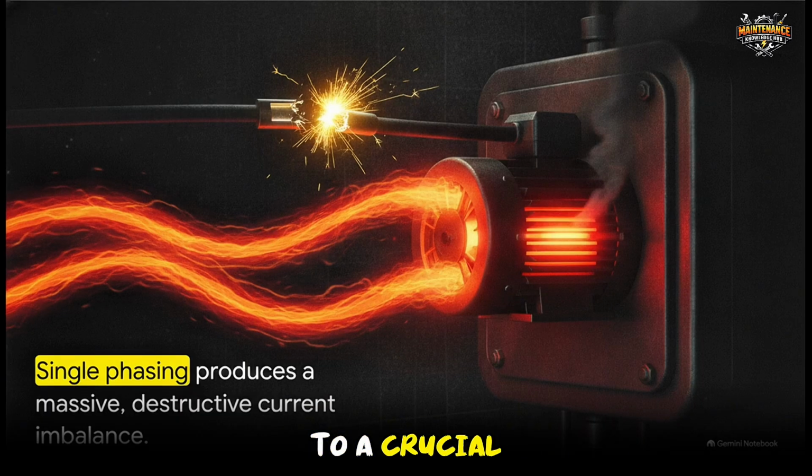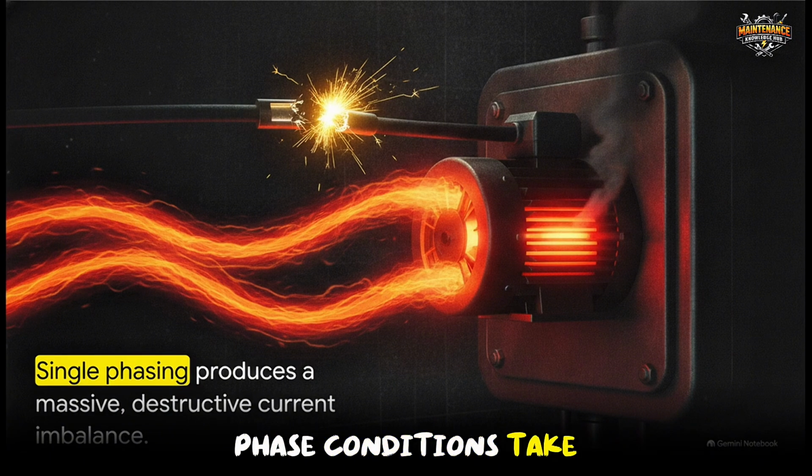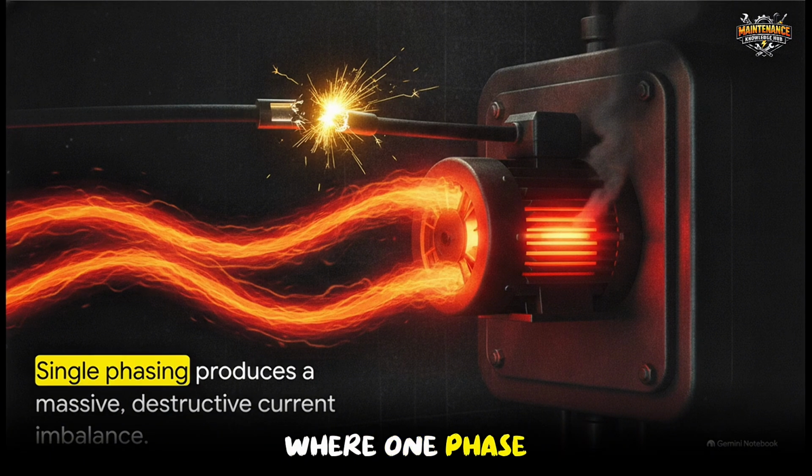This brings us to a crucial point. You must absolutely never allow a motor to operate under abnormal phase conditions. Take single phasing, for instance, where one phase of a 3-phase motor is totally lost because of, say, a blown fuse or a damaged cable. That will cause the motor to overheat rapidly or just fail to start altogether.